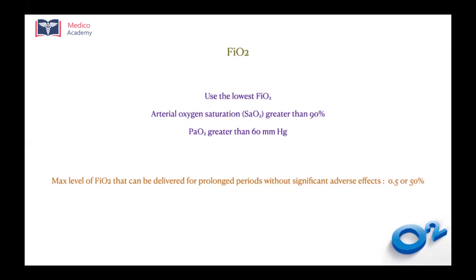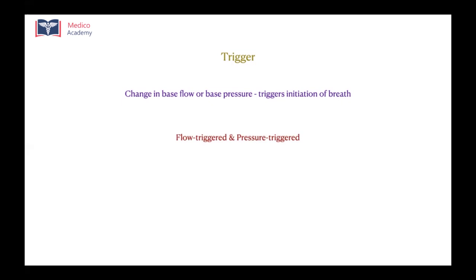So the last variable that you're going to set will be the trigger. I have discussed the trigger in detail in the lecture called modes of ventilation, but I'll explain it once again. The trigger is a variable which triggers initiation of a breath. That is, the ventilator will initiate a breath only when triggered by a particular variable. Either a change in the base flow or the base pressure triggers initiation of a breath. Most of our ventilators are either flow triggered or pressure triggered. There are ventilators in which you can set either, but most of the time ventilators come with just one kind of trigger, that is flow trigger.